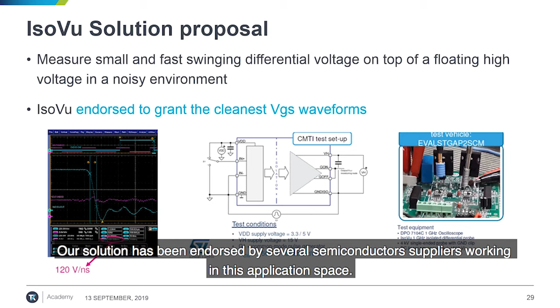And also a small differential voltage needs to be measured on top of a floating high voltage, sometimes kilovolts, with a very fast voltage swing. So a probe that accurately measures this kind of phenomenon has to be sensitive, has to be accurate and immune to disturbance noise, and must have a very high common mode rejection ratio across a very wide bandwidth, because this is imposed by fast voltage swings. So again, there is no such thing in the test and measurement world except an extraordinary solution patented under the name of IsoVu technology by Tektronix to do that. And our solution has been endorsed by several semiconductor suppliers working in this application space.